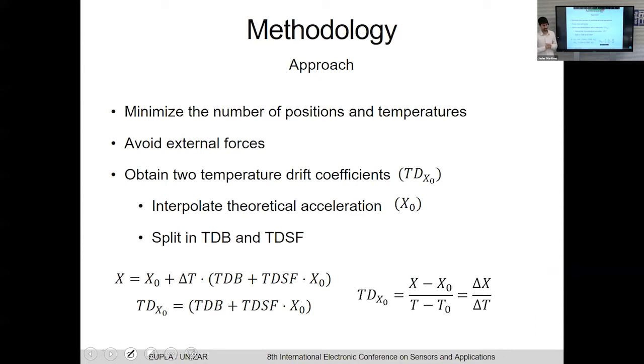Our approach to reduce the time is to minimize the number of positions and temperatures required during the test. We will do this by using all the positions to calibrate all the axes simultaneously, and we will use a contactless heat source that will reduce the thermal inertia of the system, further increasing the calibration speed. This contactless heat source also avoids any external forces. We will use the gravity force as our reference. Therefore, we need to avoid any extra stresses, and we will use only one anchor point between the board and the calibration structure.